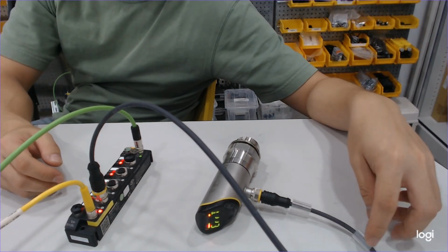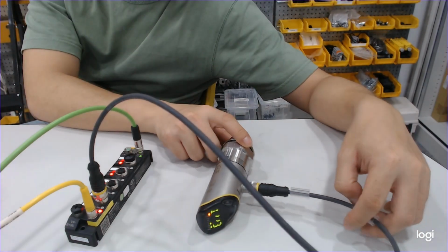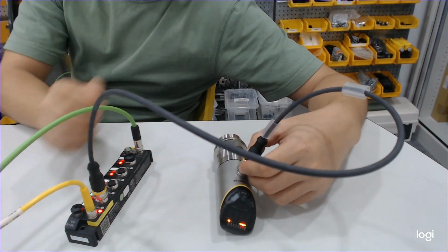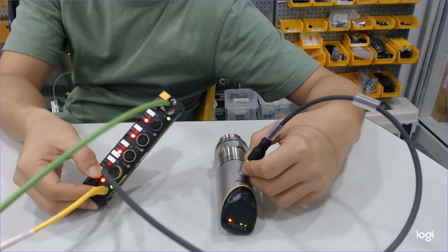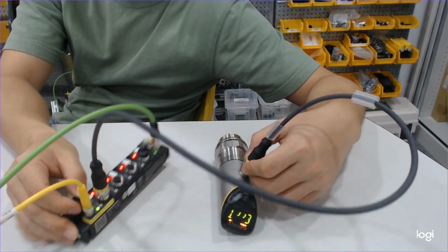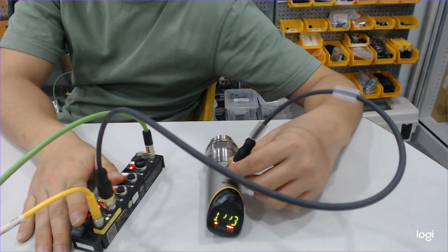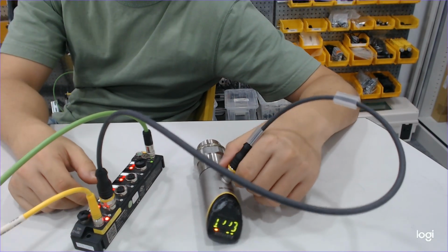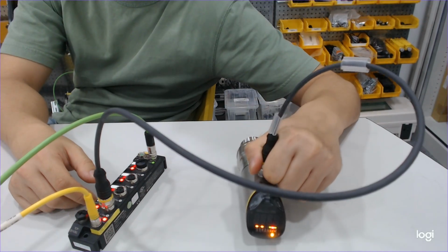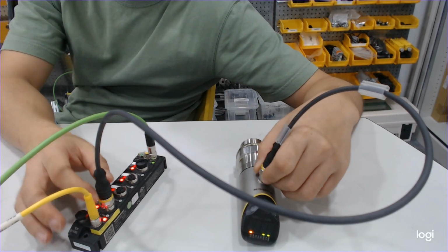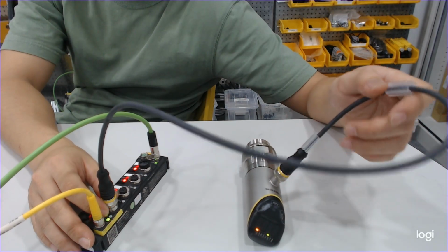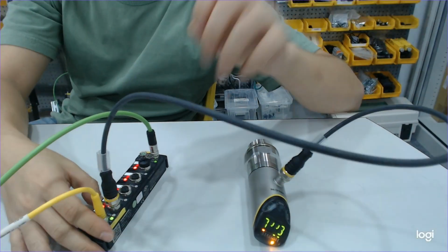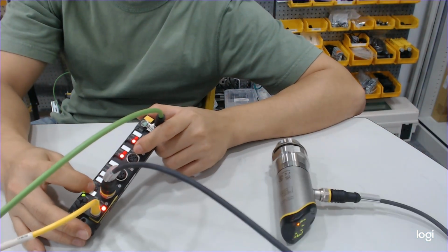I'm here from Turck Banner and I'm going to show you today how to read diagnostic data from our Turck IO-Link Master modules. So over here, I've chosen a malfunctioning, less than functioning sensor. This is a radar sensor that is not functioning correctly because I have not parameterized it correctly. It's connected to the IO-Link Master, which you can see is showing an error over here.